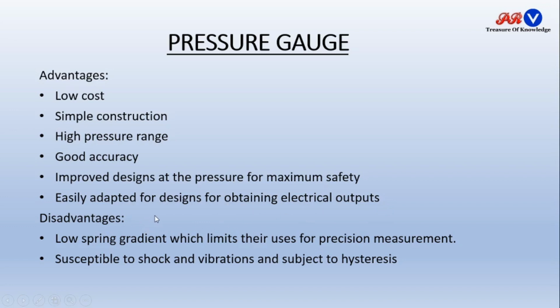Disadvantages: it has low spring gradient which limits its use for precision measurement. Spring gradient is low, so we are not able to precisely measure the pressure. It is also susceptible to shock and vibrations, so it will create errors, and subject to hysteresis.